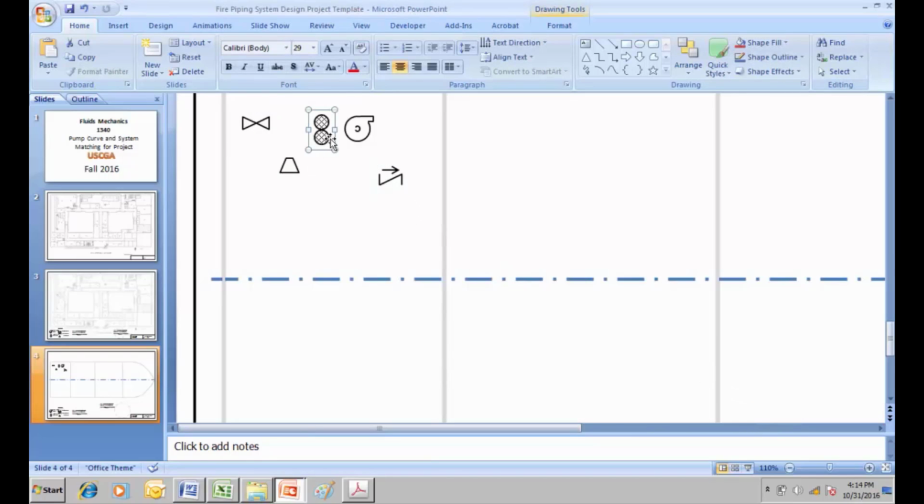And this is a strainer, a duplex strainer. That means there are two strainers side by side so that you can keep the system operating and just shift over from one side to the other. There's a big handle, and you can open up one of the strainers and remove the basket and get all the little fish, marine growth and so forth out of there.